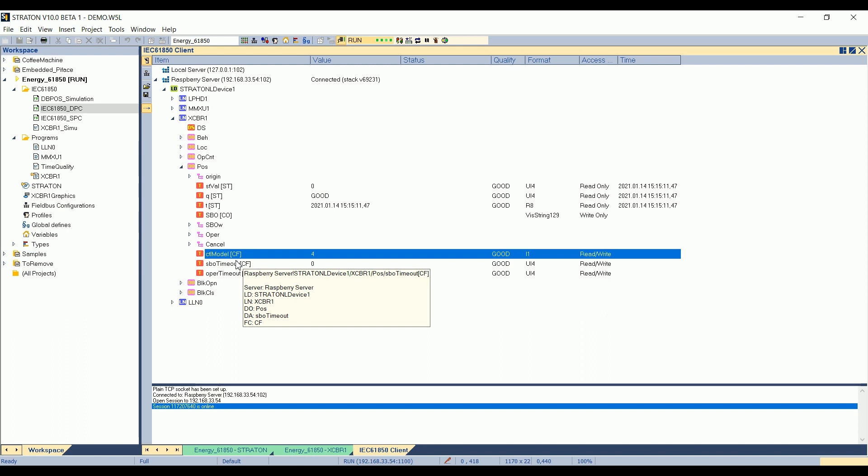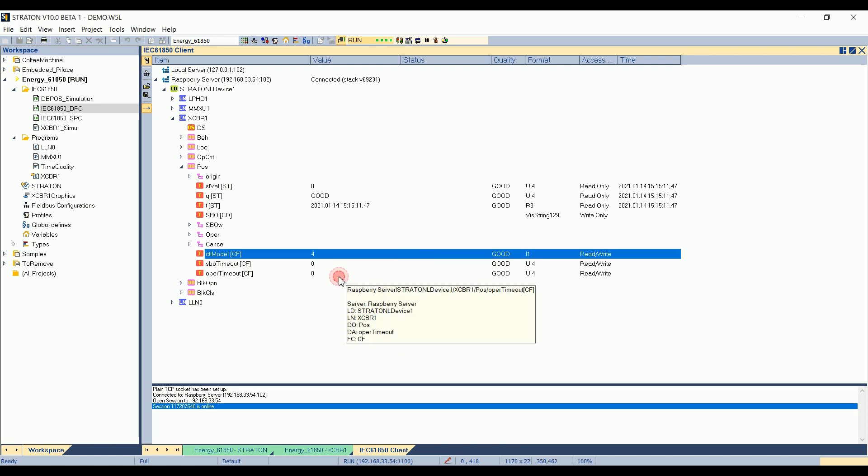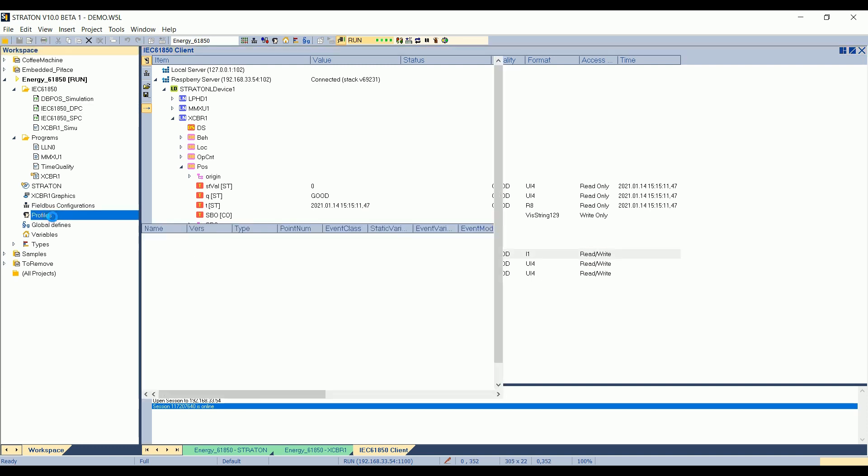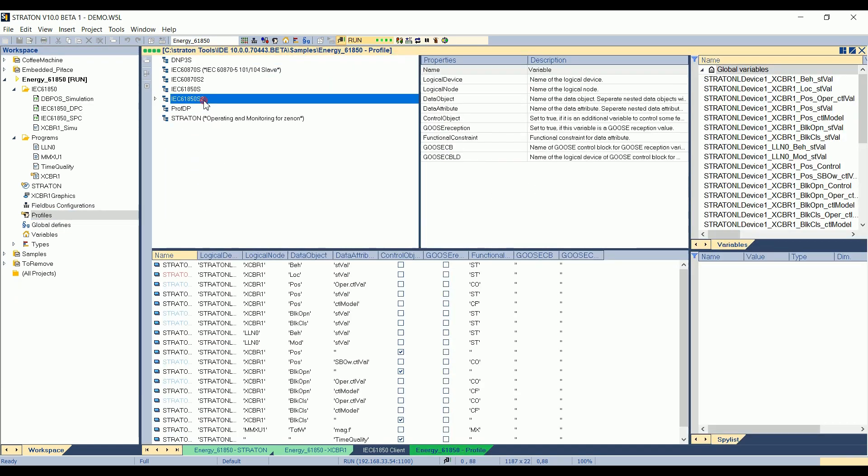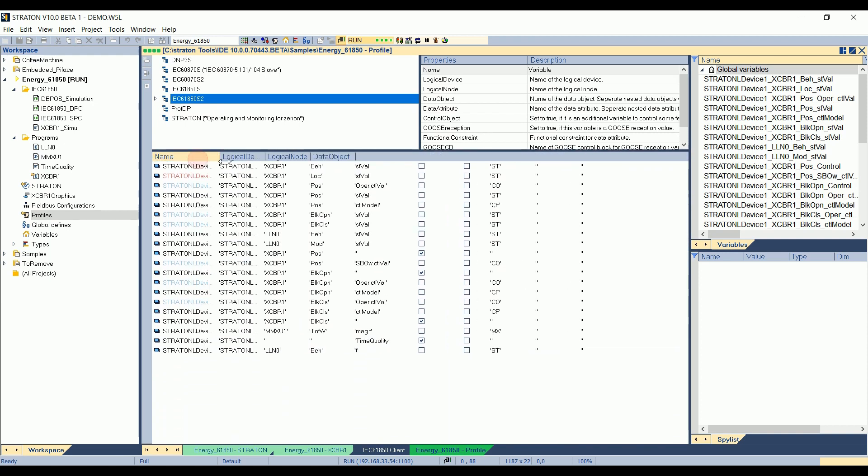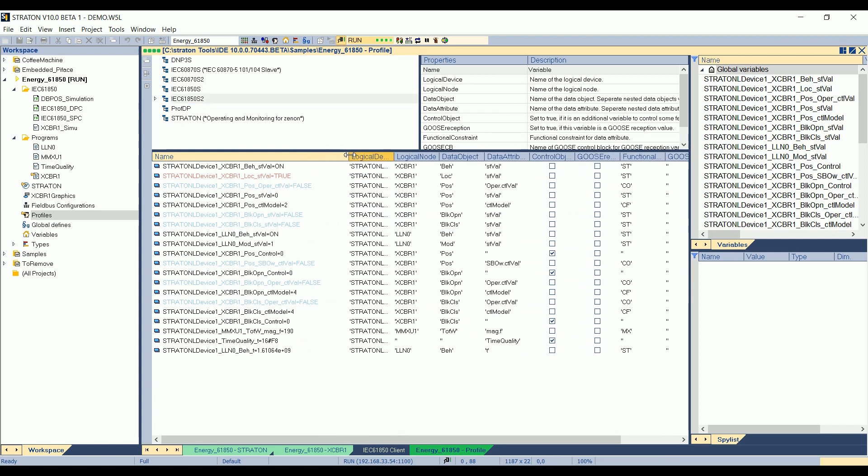The control model has the functional constraint CF. It means configurable, so I can force it from the client. If I want to force it to another value, I just double-click on it. I choose, for example, control model 2, select before operate with normal security. I double-click on it. Quickly, writing has been displayed. I can see that now control model is equal to 2. And if I check on the server side in my Straton application, for example, here, I open the profiles to see my 850 server variables. There are several variables already declared in the application. I expand this column. And here, somewhere, I have my Straton logical device, circuit breaker 1, position, control model equal to 2.